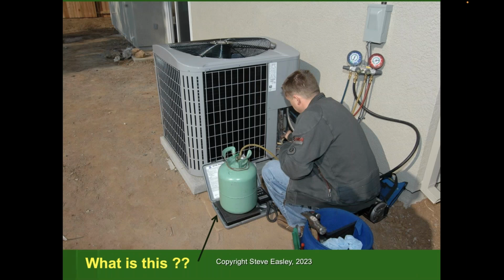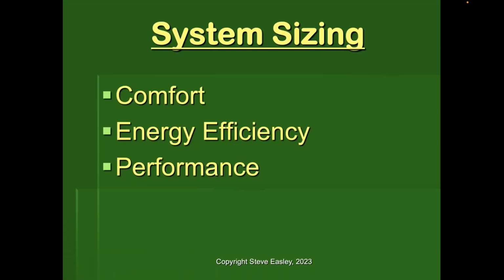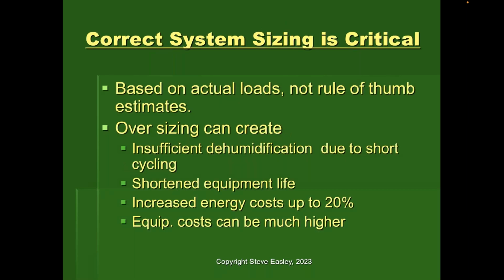That means they're using digital gauges, not analog gauges like we see here, and they're weighing in the refrigerant. You have qualified people who know what they're doing, to make sure we're putting in the right amount of refrigerant, that we're not just filling it up, so that the refrigerant charges properly. So getting the sizing right is good for comfort, for energy efficiency, and performance.